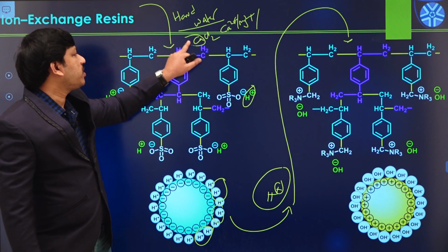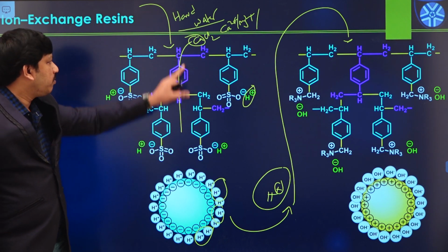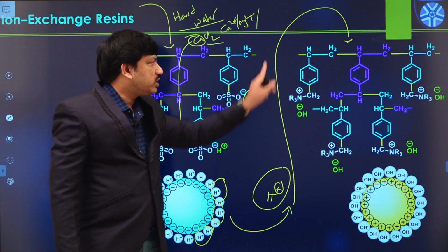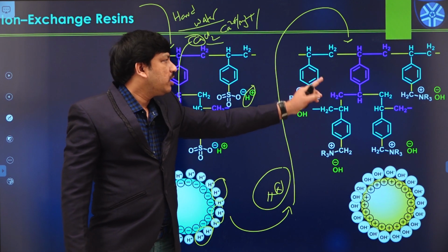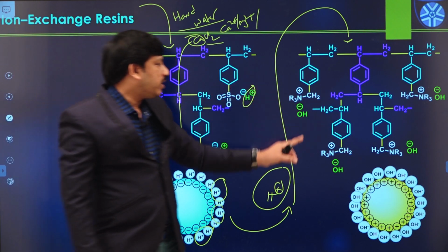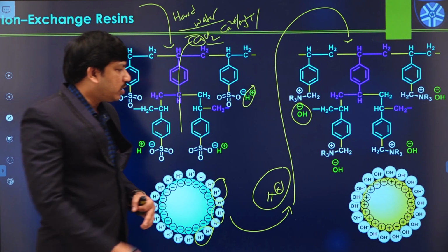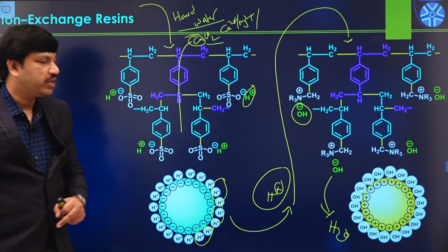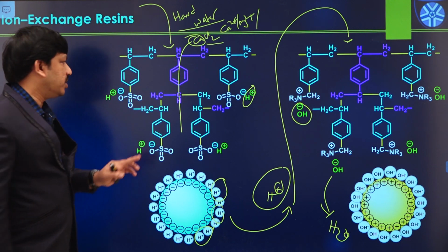The calcium cation is removed in the first step, but the solution still contains Cl minus ions. That water goes to the second exchange resin, and here all types of anions are completely removed because of the exchange of OH minus with any other anion. The remaining water is called demineralized water. So in this process there is a need for two different reagents.